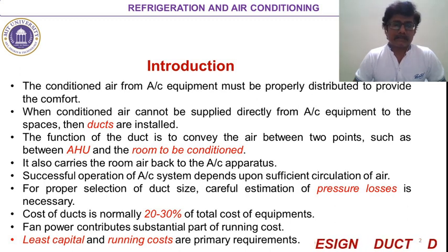And it should also be taken into consideration that the cost of the duct is normally 20 to 30% of the total cost of the equipment. So one-fifth to one-third of the cost of the equipment is borne by the ducts only. So ducts form a very major, important element in central air conditioning systems.